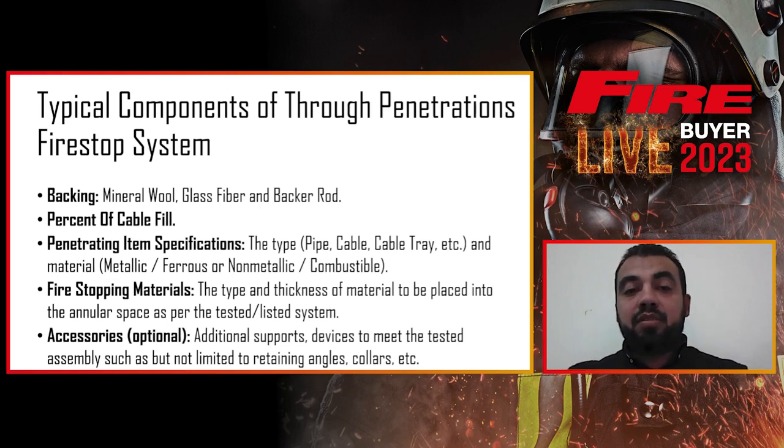Another very common error we see on fire inspections is the percent of cable fill. This is the cable fill on the opening or the cable fill over a cable tray, and also the type of cables that you have on site. If you have a higher percentage of cable filling, this will be an issue for your material to react, stop the fire properly, and perform as intended. So the cable filling is a very important factor that you need to focus on site. This is the percent of cable filling.